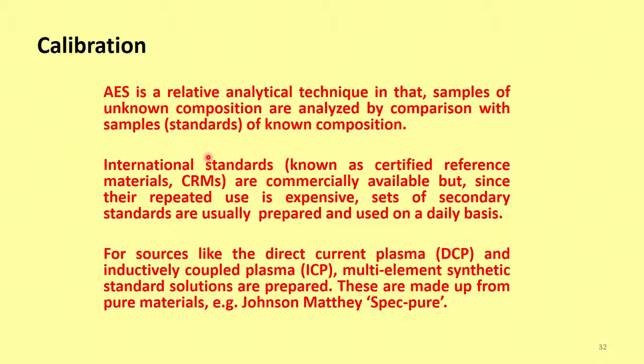So, there are international standards marketed, available for a price. These are known as certified reference materials, CRM, and sometimes we also call them SRM, standard reference materials. They are also commercially available, but since they are for repeated use, these things are very costly.